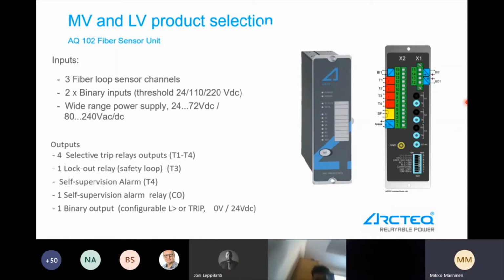Okay, this is very similar, only with the fiber unit. So here we have 3 channels for the fiber, and maximum length is 40 meters, and then there is the one special fiber which is 50 meters. But for example, for a low voltage switch board, let's say that we have 3 fiber sensors which are 40 meters each, then it is more than enough for one easy low voltage board.